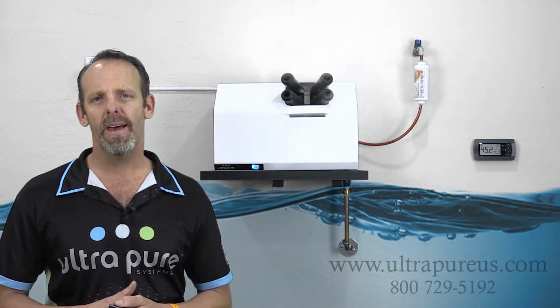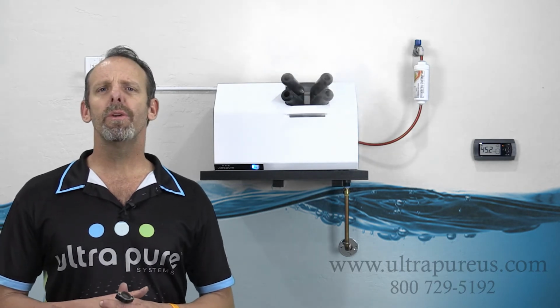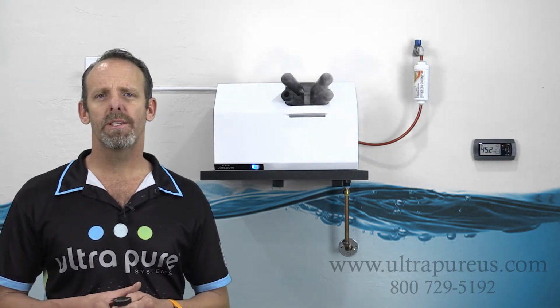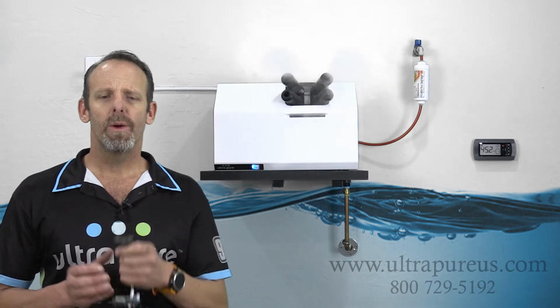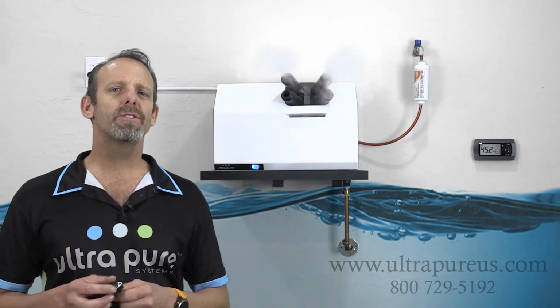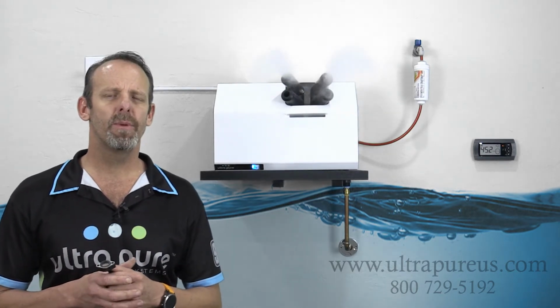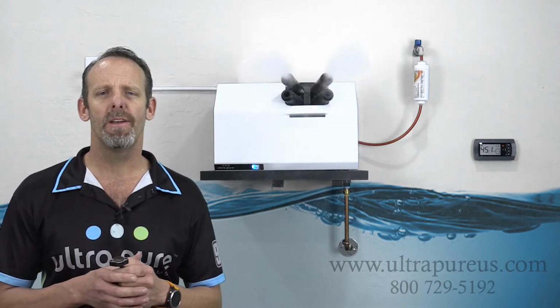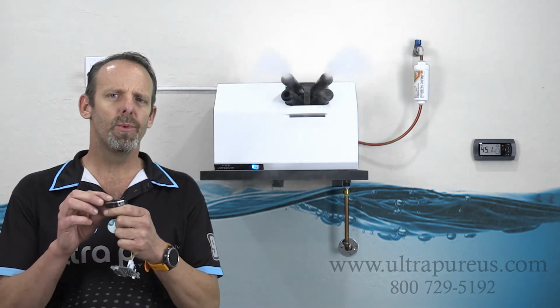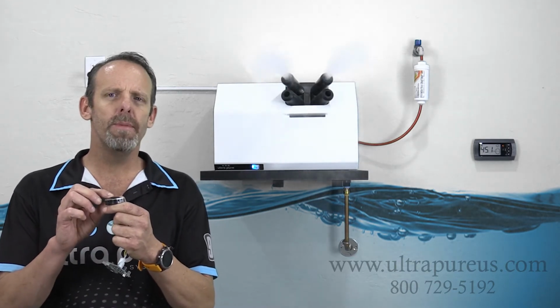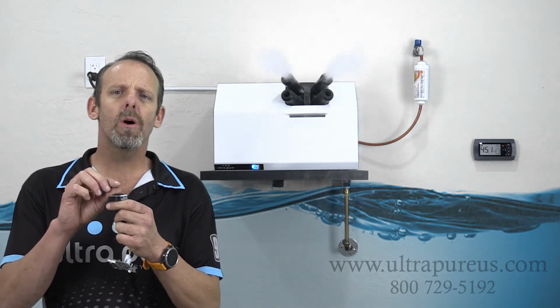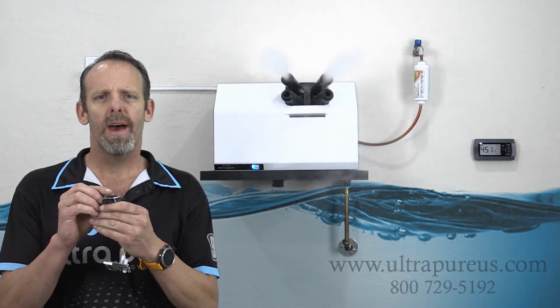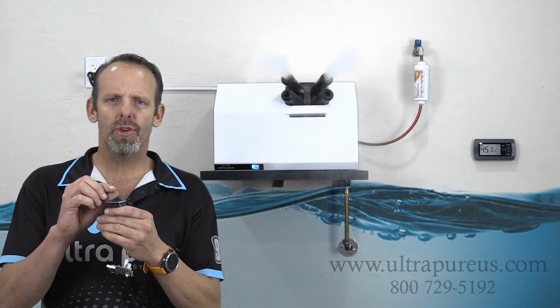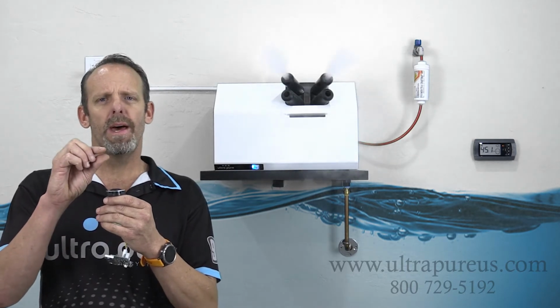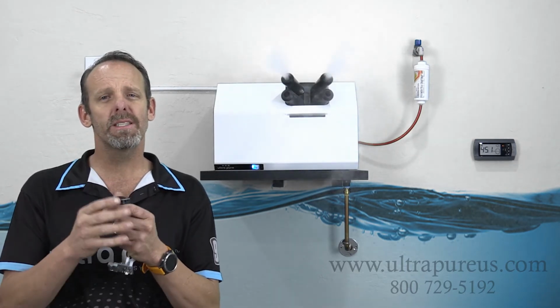Ultrasonic doesn't work like that, though. We're utilizing a mechanical means to generate the mist with the transducer—if you haven't watched the video on how ultrasonic humidification works, I'd encourage you to do that. The transducer fires and makes the mist: a very small column of water travels up and breaks on the water bed, and that's where your mist is.